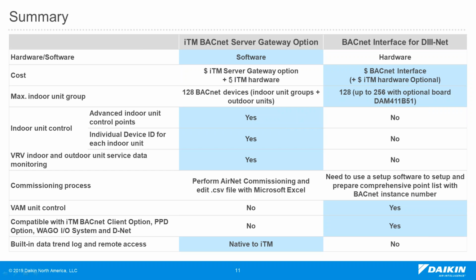But for using the ITM server gateway option, it's mandatory to have the ITM hardware, whereas for the BACnet gateway, the ITM is optional. So the BACnet gateway may have more cost efficiency if you didn't add the ITM in this project. Otherwise, the cost is about the same.